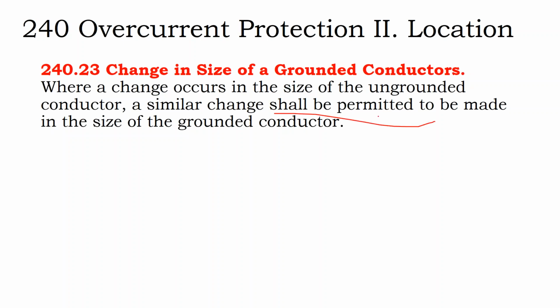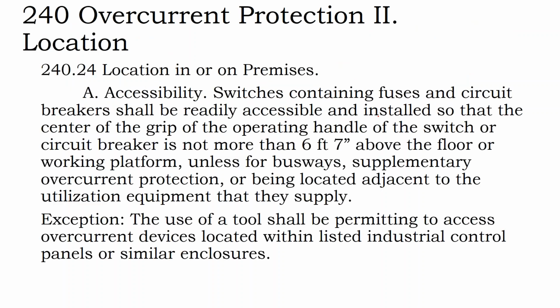You're permitted to. So there's certain cases where, like that DC bare copper ground of number 6 going up to the rooftop to ground your system, that's more than sufficient. That's to ground your DC solar racking. So you don't necessarily have to in all circumstances. And so in your balance of system material, you go to Home Depot, it's common to find wires where you might find that you need a number 8 cable, and the only Home Depot wires there have a number 8 positive, a number 8 negative, and then an undersized ground or an undersized neutral. That may or may not work for your system.